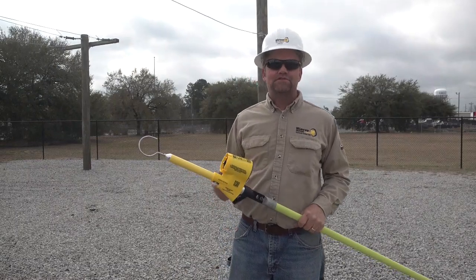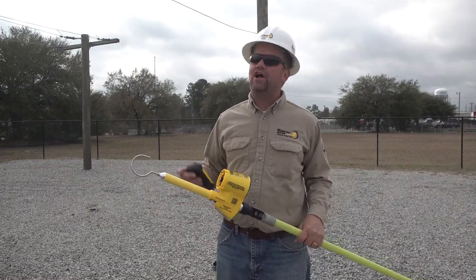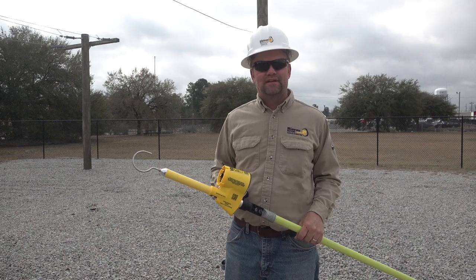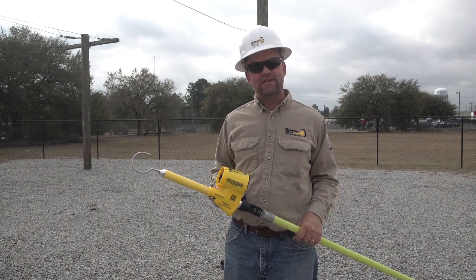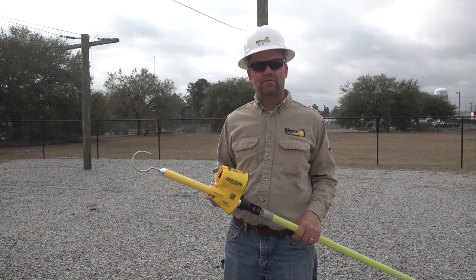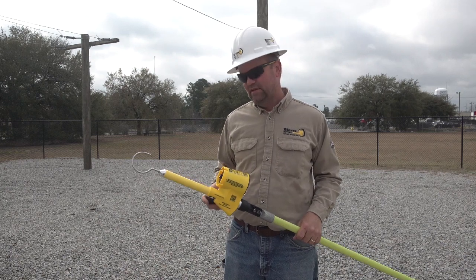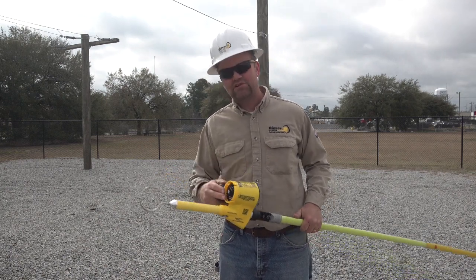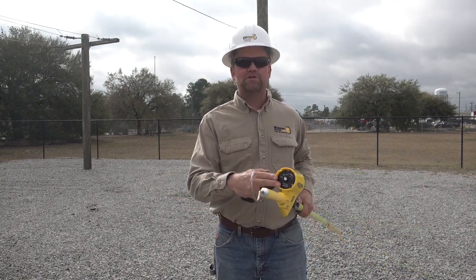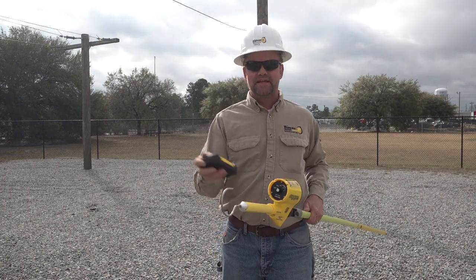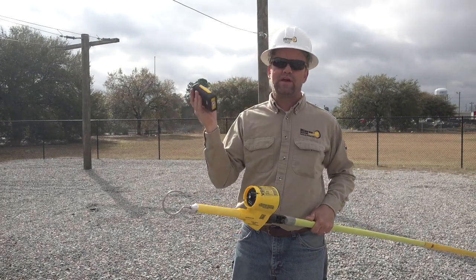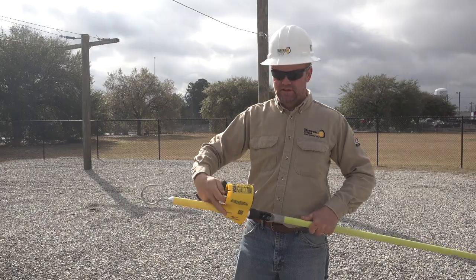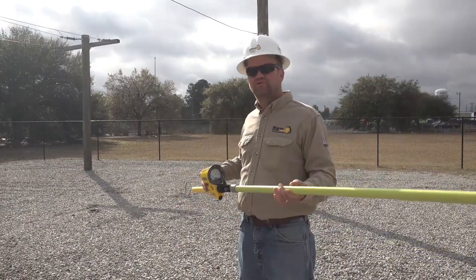Okay, now we're going to use the VDAH300 in an overhead application. Again, it's 13.8 kV phase to ground. That's our nominal voltage in our training yard. Again, I want to put our VDAH300 in the first on switch position. And again, I want to test the tool before and after I use it. So I want to make sure the tool's functioning properly.